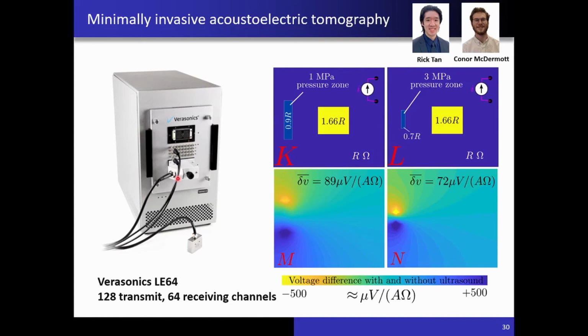So the machine will be used for two purposes. The first one is, of course, to control the ultrasonic pressure using acoustic radiation force impulse. And the second use of this machine is to use its receiving channels as electrodes. So the needles will be connected directly to the inputs of this machine, which will give us a much higher accuracy in voltage readings and also a wider frequency range.